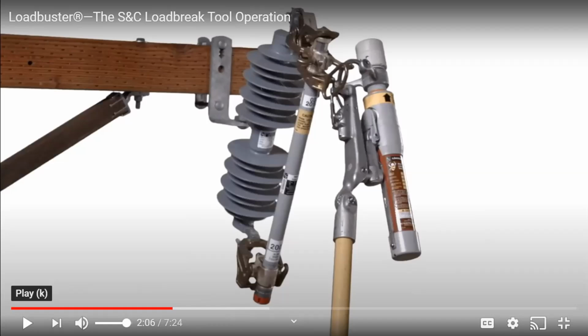When you say nominal, I mean, the tool's not going to last forever, right? It's load busting. If you go up to 600 amps and you're using it regularly at 600 amps or below, you can use the tool for a good while. It will break 900 amps when needed, but you're definitely going to be starting to degrade the tool. And to be honest with you, there's no really good way to test it without taking it apart and seeing the load break mechanism inside, see if it's arcing or melting or whatnot.